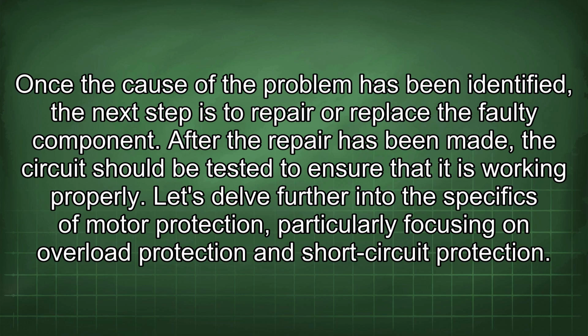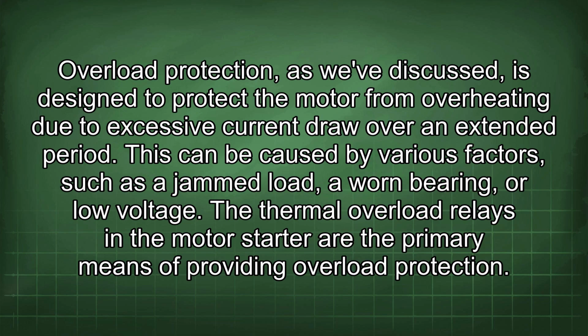Once the cause of the problem has been identified, the next step is to repair or replace the faulty component. After the repair has been made, the circuit should be tested to ensure that it is working properly. Let's delve further into the specifics of motor protection, particularly focusing on overload protection and short circuit protection. Overload protection, as we've discussed, is designed to protect the motor from overheating due to excessive current draw over an extended period. This can be caused by various factors such as a jammed load, a worn bearing, or low voltage.